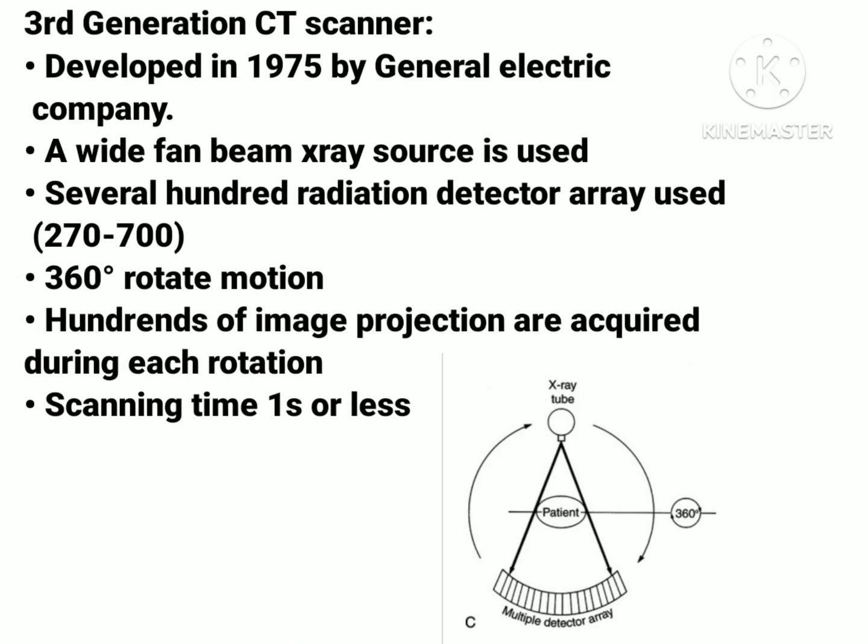The third generation CT scanner was developed in 1975 by the General Electric Company. In this generation, scanners needed to be faster and required elimination of translation motion, so that smoother and simpler pure rotational motion could be used. For that, a widened X-ray beam — a wide fan beam — was used as the source. The detector array is rigidly linked with the X-ray tube, so both the X-ray tube and detectors rotate around the patient. This motion is referred to as rotate-rotate.